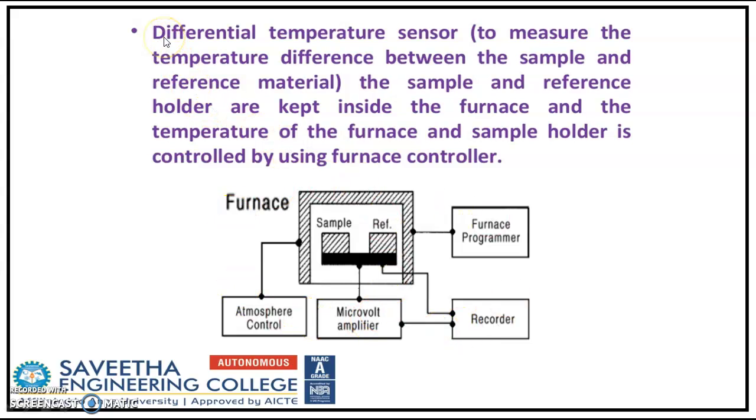Here the differential temperature sensor is also there. It is used to measure the temperature difference between the sample and the reference material. This is very important. This part plays a very important role. The differential temperature sensor plays a very important role in DTA.